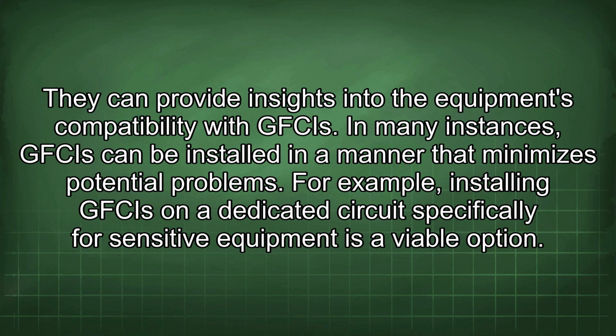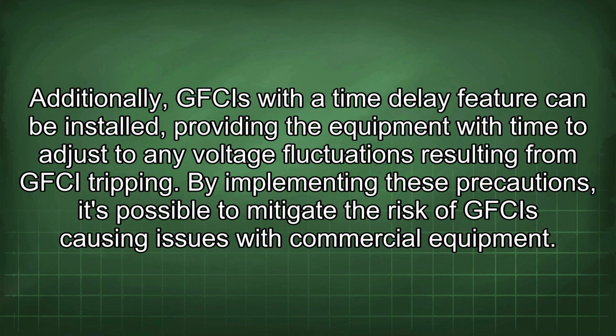In many instances, GFCIs can be installed in a manner that minimizes potential problems. For example, installing GFCIs on a dedicated circuit specifically for sensitive equipment is a viable option. Additionally, GFCIs with a time delay feature can be installed, providing the equipment with time to adjust to any voltage fluctuations resulting from GFCI tripping. By implementing these precautions, it's possible to mitigate the risk of GFCIs causing issues with commercial equipment.